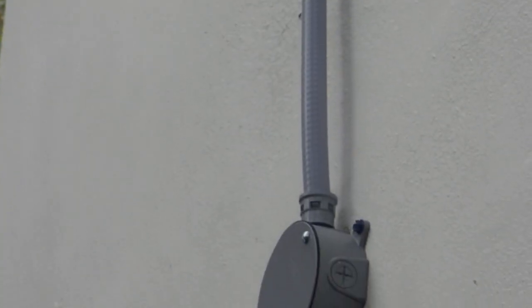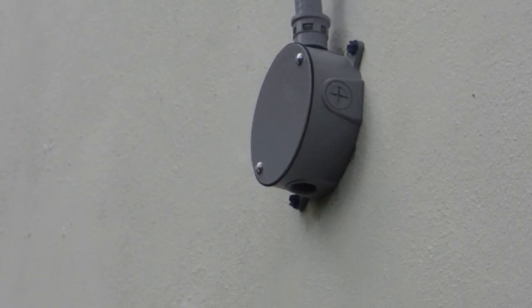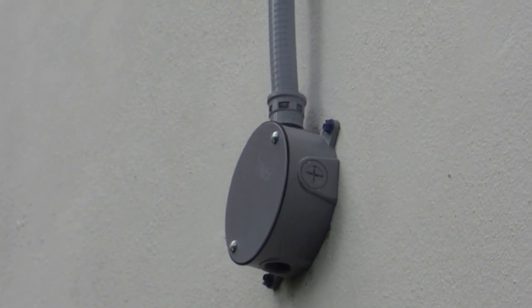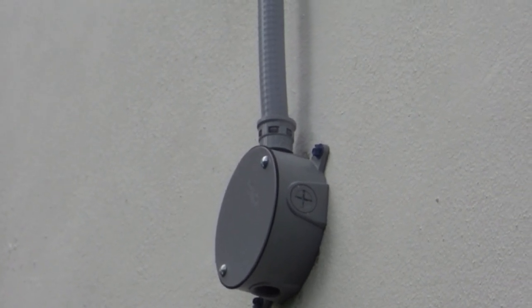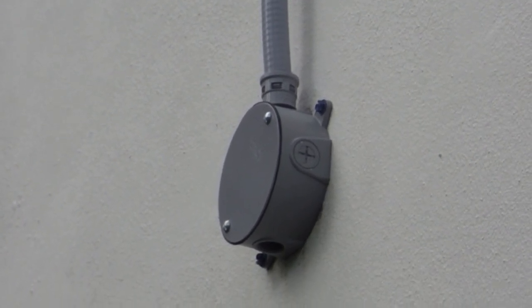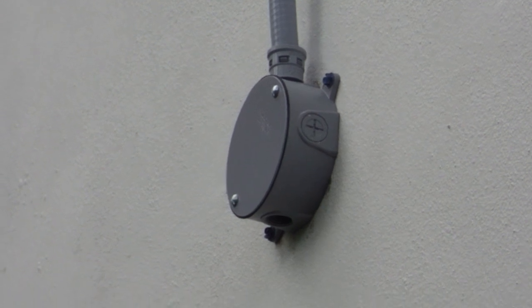So, not enough supports or clips on that raceway and the wrong types of connectors used for that wiring method.